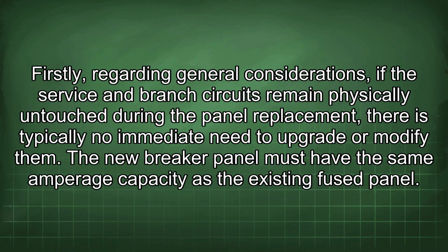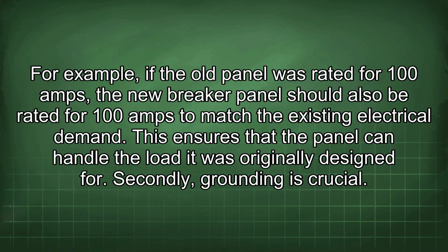Firstly, regarding general considerations, if the service and branch circuits remain physically untouched during the panel replacement, there is typically no immediate need to upgrade or modify them. The new breaker panel must have the same amperage capacity as the existing fuse panel. For example, if the old panel was rated for 100 amps, the new breaker panel should also be rated for 100 amps to match the existing electrical demand. This ensures that the panel can handle the load it was originally designed for.